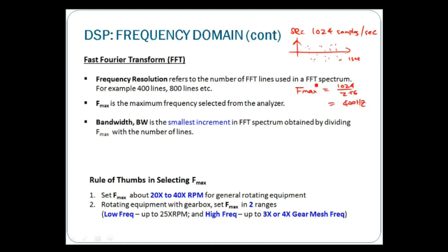So if you want to convert this through FFT into amplitude, this is amplitude over time, and this is amplitude over frequencies. Because of these anti-aliasing filters, you won't get 1024 hertz. You only get less than half of it, and because of the oversampling due to these analog low pass filters, you get less than half. So it's 2.56, 400 hertz.